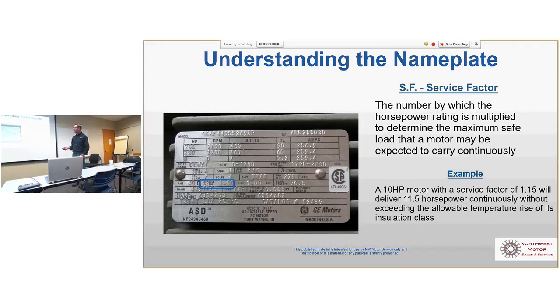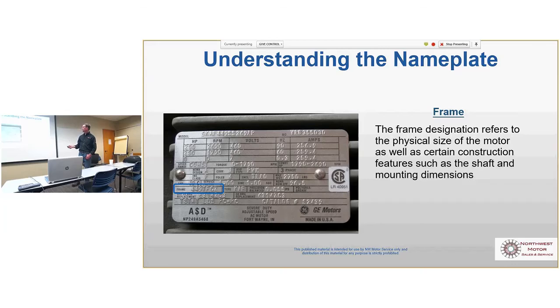Frame size, that's really important. We're going to talk a lot about frame sizes here in a second. That's a NEMA standard all manufacturers have agreed to use, like everybody's 5 horse 1800 RPM motors are 184T by standard, no matter who's the manufacturer. So that makes it really easy if I'm replacing a Reliance or a Baldor with a GE or vice versa. It's all interchangeable, with a couple exceptions.